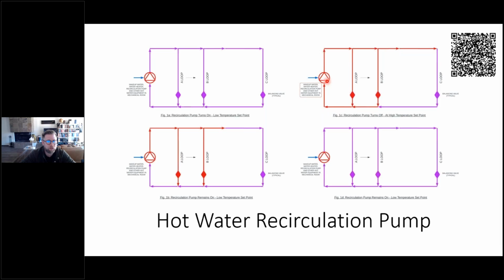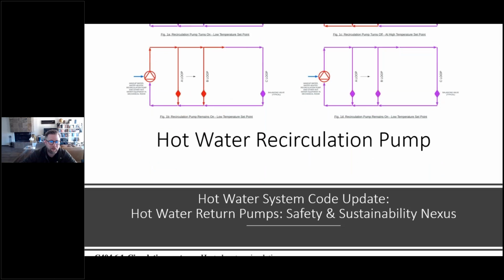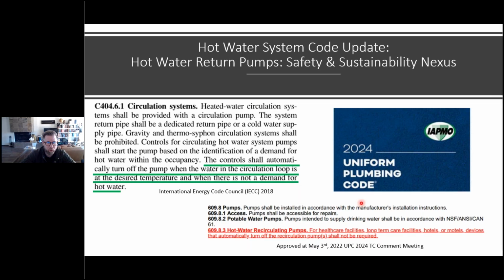You get that water back to the water heater, and the aquastat turns off, and now your system starts to cool down before the pump re-engages. But what you'll notice is the C loop never quite gets to a hot temperature. That red piping never gets that hot temperature, which could mean that you have waterborne pathogen growth in that C loop, because it's in essence not balanced or not designed in such a way that will ever get flow. This was actually part of the discussion in the 2024 Uniform Plumbing Code because enough engineers were having a problem with the International Energy Conservation Code in shutting off the pump with aquastats, and trying to supersede sometimes, and having arguments with the AHJ about which one should get installed.